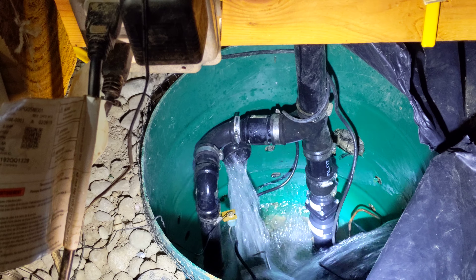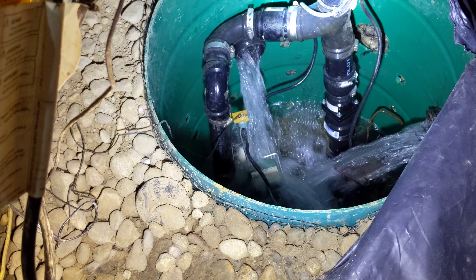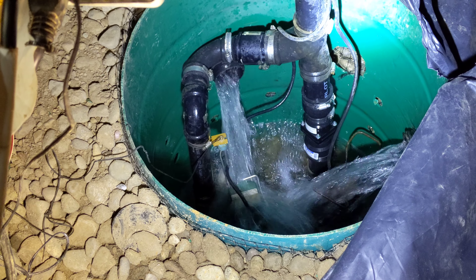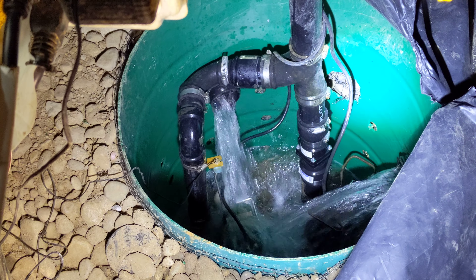I think these two pumps are working non-stop. Even this cable is a little warm. There is an alarm as well — the yellow one — and if the water hits that level, the alarm will ring. When we unplugged one of the pumps this afternoon, it was probably taking only 10 to 15 seconds for the two pipes to fill the bucket and trigger the alarm. It felt pretty crazy.